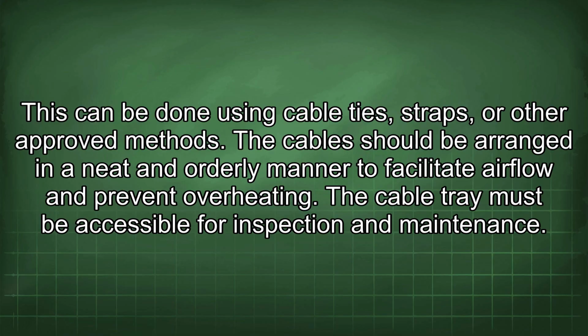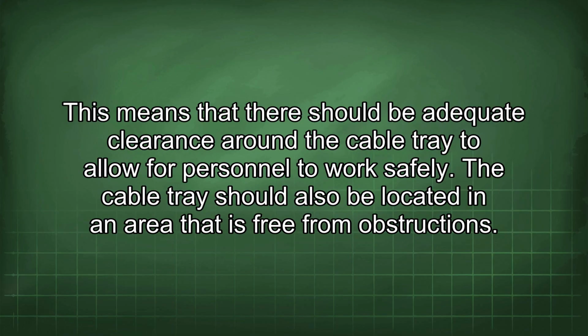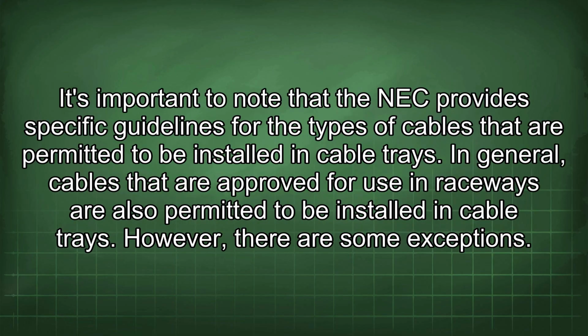The cable tray must be accessible for inspection and maintenance. This means that there should be adequate clearance around the cable tray to allow for personnel to work safely. The cable tray should also be located in an area that is free from obstructions. It's important to note that the NEC provides specific guidelines for the types of cables that are permitted to be installed in cable trays. In general, cables that are approved for use in raceways are also permitted to be installed in cable trays. However, there are some exceptions.